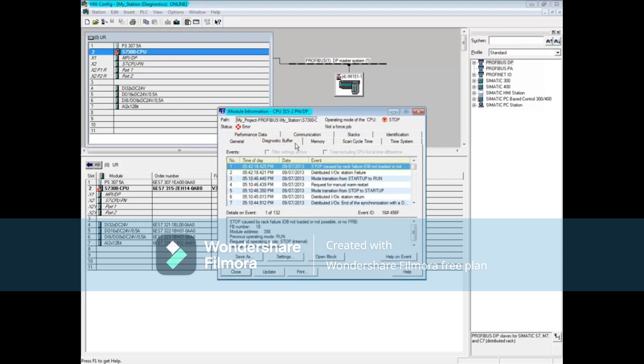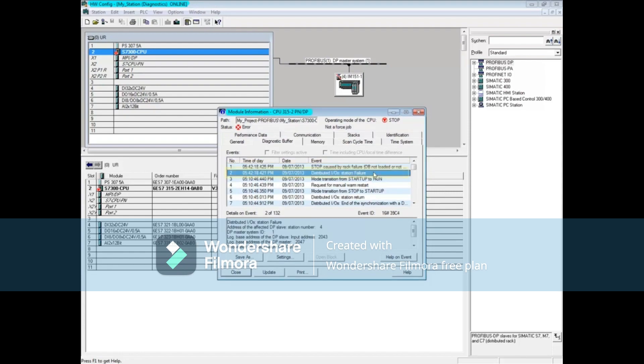Message 1 shows that the CPU is in stop mode because of a rack failure. Message 2 says that the distributed I/O station has failed. In the Details window, the DP station that went down is number 4 and is part of the Profibus Master System 1.